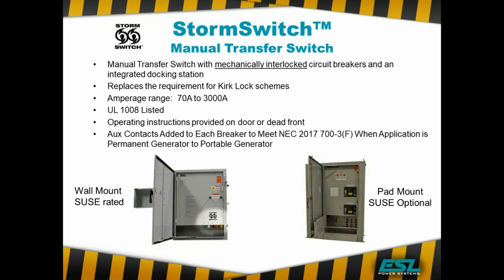Also, from a design standpoint, the wall-mounted units come service entrance rated standard. So if you're at 800 amps or below, the unit comes service entrance rated, so you don't have to design in a separate disconnect if you're using this to switch between utility and a portable generator. The utility breaker on this unit can be the service disconnect. So again, it saves you a little bit of money, saves you a little bit of installation costs, and makes it very efficient. On the pad mounted units, service entrance rated is an option. It adds a little bit of cost to the unit, and we don't want to charge people for something they don't need, but these can come service entrance rated. We just have to know if you're going to use it that way.